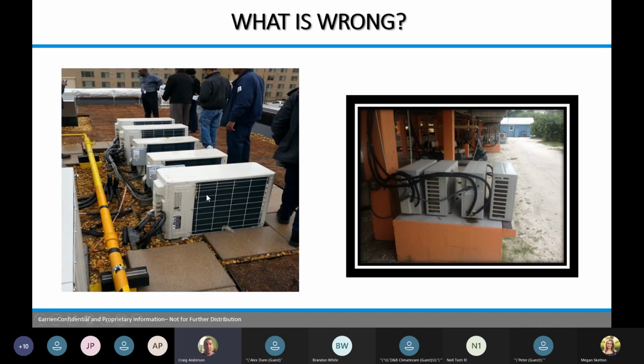This is another big thing, guys, too. If you're going on calls that have multiple units outside or beside the house or on the roof, it's nice to put them all in a line. They have clearances. Look at the clearances in the book. If we start with one unit, this unit's blowing into this one, and this one's blowing into this one. So once we're getting in the center and on the far one, somebody's overheating at some point. So we're going to get erratic behavior on the sensors and the operation. It could overheat the compressor. It could overheat the fans.